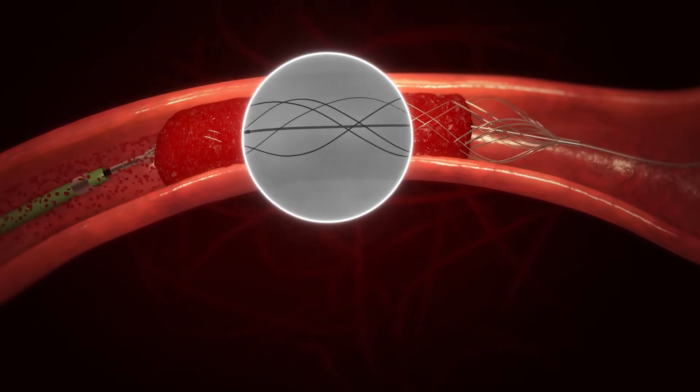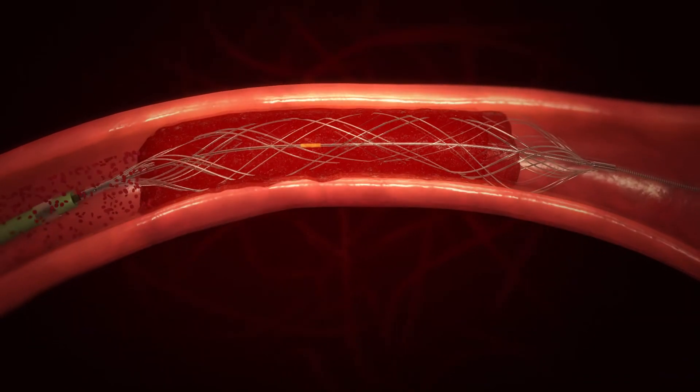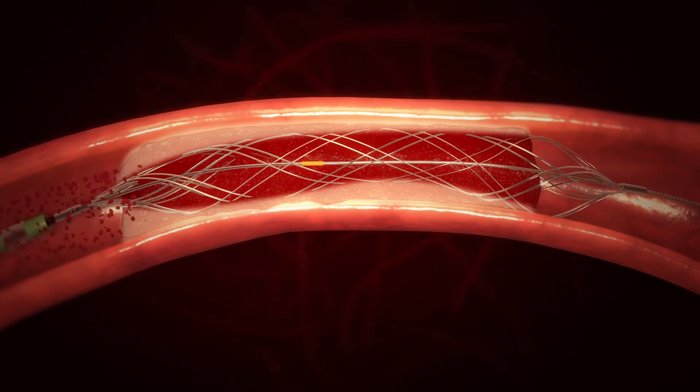The clot is contained using three complementary methods. The radial force creates friction between the clot and the braided net.